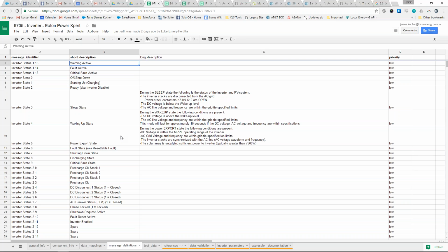The short and sweet version is integers are the actual values that you see on the AquaSuite. So if you see an integer mapping, it means if the AquaSuite shows 10 and the mapping says 10, that fault will be represented. For bits, it's a little more complicated than that. The value of bits is you can have multiple faults in a particular register, whereas with the status, it's either 10 or 9 or 8. With bits, you can actually have superimposed statuses. Pretty much what it comes down to is a bit of 0 means that the AquaSuite will have a value of 1 as part of the summation of that register.